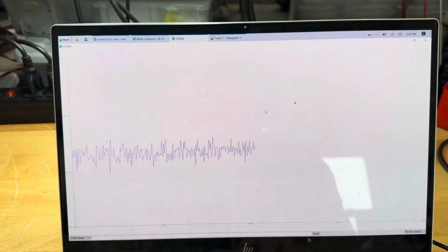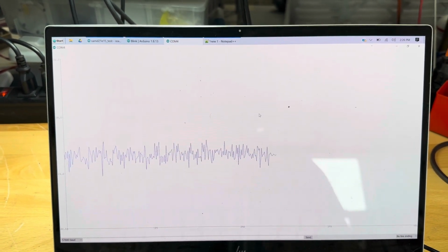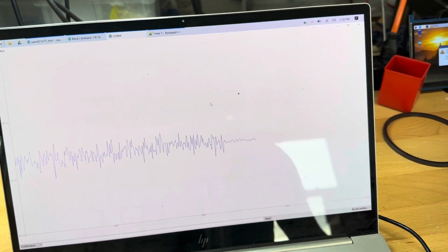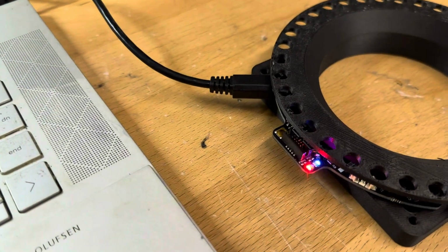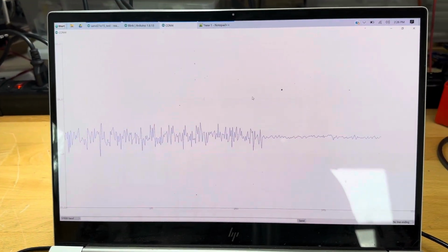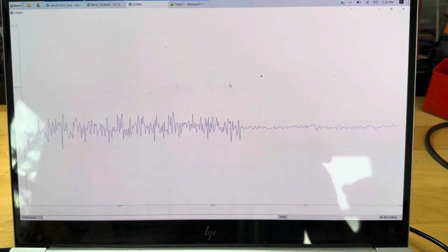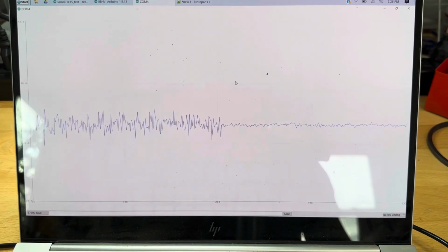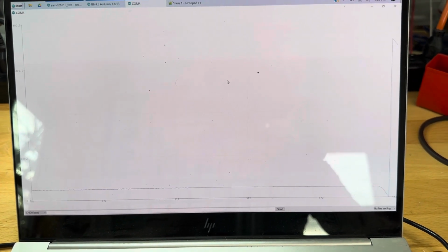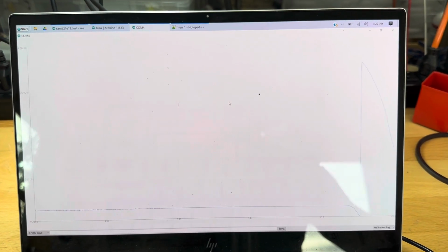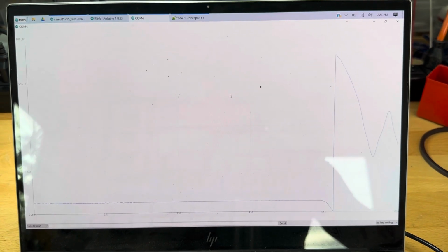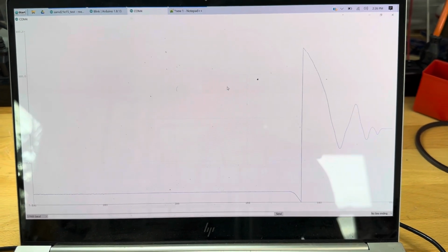I'm going to send an F and hit enter, and you'll see the data calm down quite a bit. Now the blue light is blinking. There are 4 steps of filtering here; you just keep sending Fs and it's a more and more aggressive filter. Remember, any filter is going to slow the sensor data down, so you may not want to do this internally on the sensor, but the sensor does provide it for you.